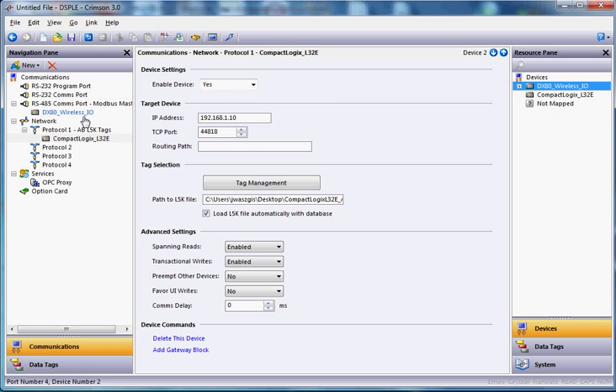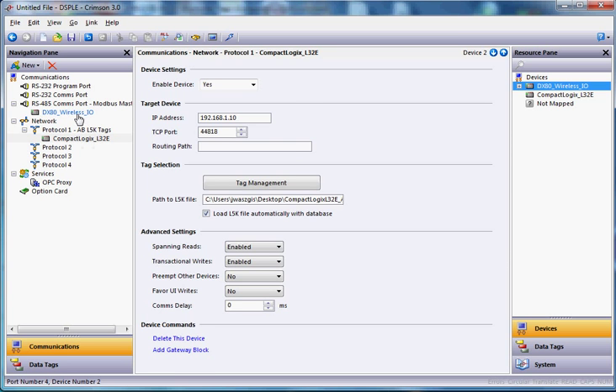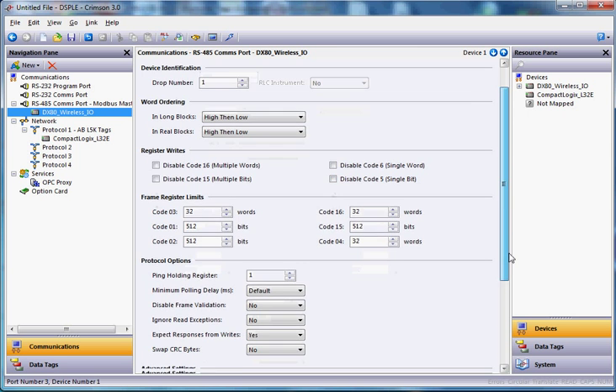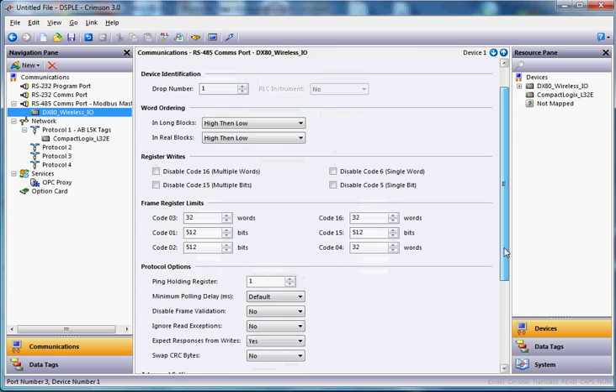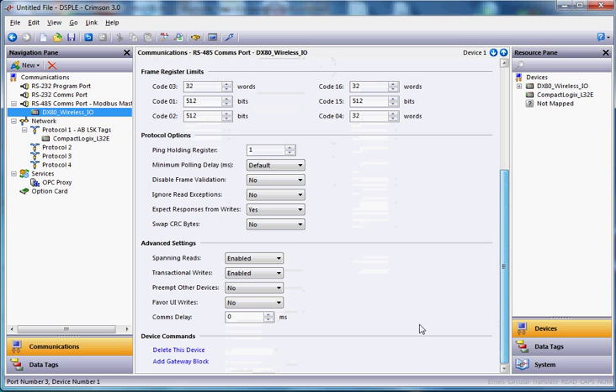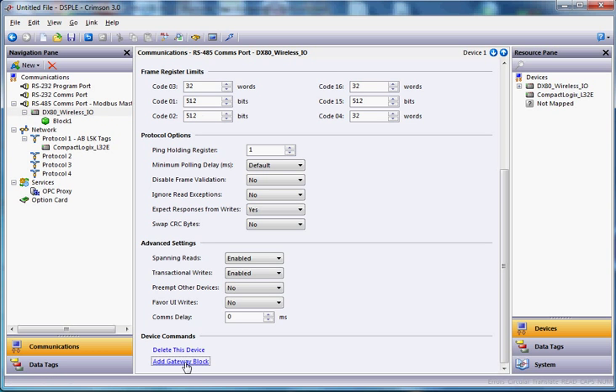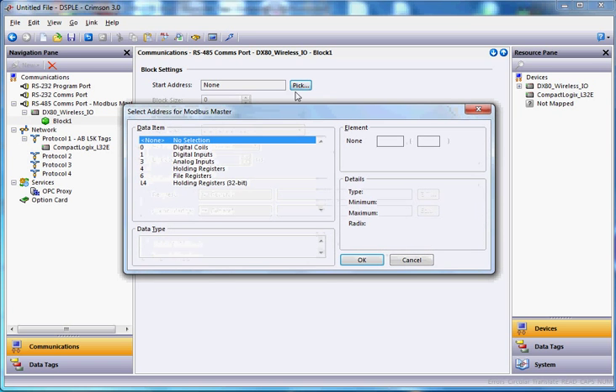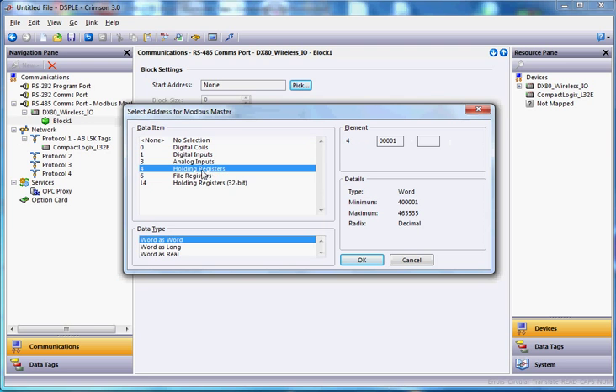Now, the goal is, again, to get input data from the wireless world and put it into the CompactLogix. And when the CompactLogix wants to turn something on out here, to have it go out to this guy. So I'm going to go over here to the wireless, DX80 wireless node right here, and I'm going to grab the little slider bar over here on the right-hand side of Crimson, and I'll slide down a little bit, and way down below, you're going to see a section here that says Add Gateway Block. So I'm going to click on the Add Gateway Block here. I get a green block underneath here. If I click on that block, I'm going to hit the Pick button, and everything in the Banner products will be in the holding registers. So I'm going to click here on holding registers. I'm going to start the first one, 40,001, and click OK.